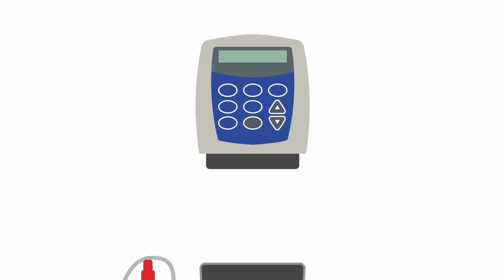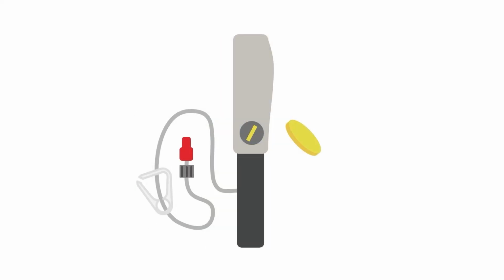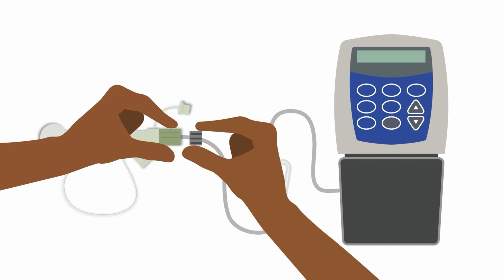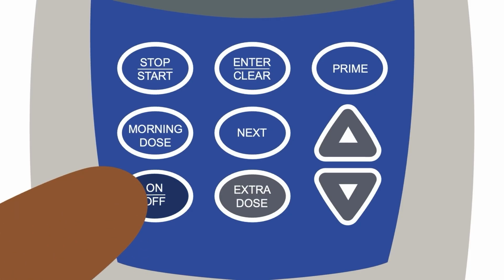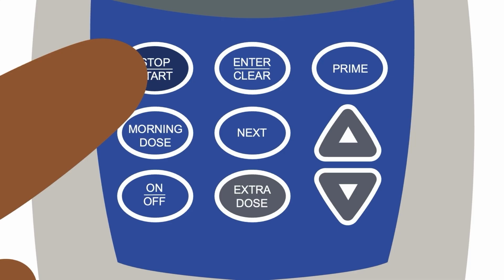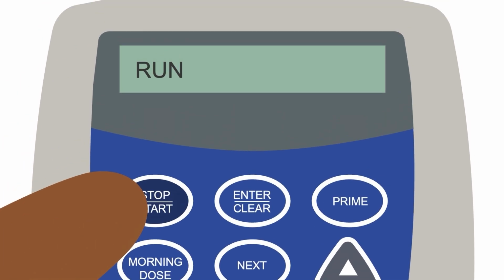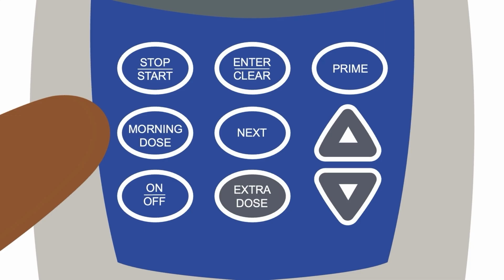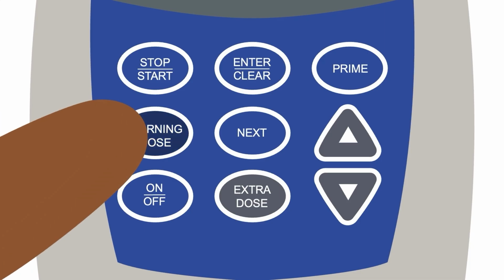In the morning, you need to connect a new cassette to the pump and use a coin to lock it on the side. Remove the red protection cap from the cassette tube and open all tube clamps. Connect the cassette tube to the PEGJ intestinal port connector. Make sure to twist the cassette tube rather than the PEGJ tube. Press and hold the on-off button for 3 seconds until it turns on. Press and hold the start-stop button for 3 seconds until the text "Run" is shown on the display. This indicates that the pump is running. Press the morning dose button twice to administer the morning dose. After finishing the morning dose, the continuous infusion will start automatically.